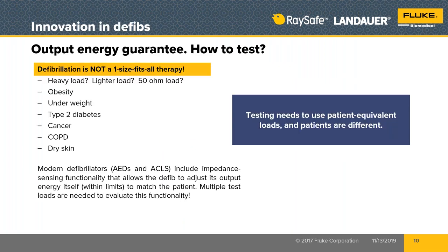Hey, Jerry. Yeah. We had a gentleman ping in here saying that their defibs are tested every day. And I can't help but think, but this is, you're right. In most medical facilities, they do a daily check in all your crash carts and your defibrillators. But are you really going through all the parameters when they do that? Or are they just powering them on, making sure it powers on and the battery's full and the pads are still in service? Right. So those tests are done for sure, but they're not done by the biomed typically. They're done by nursing, or in the case, Justin, of ambulance services and air medevac, they're done by a flight engineer or someone on a daily routine. But typically, those would be done by the clinical staff. The twice per year is what the biomed is going to do.